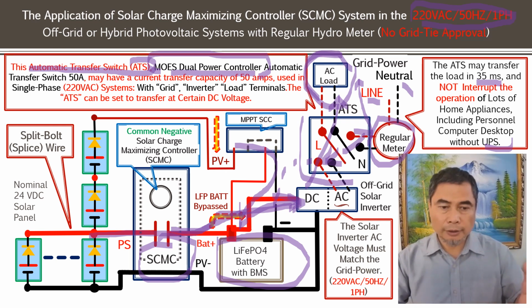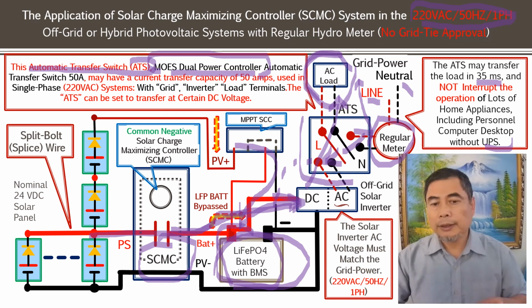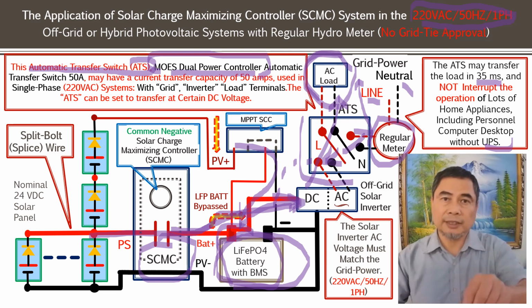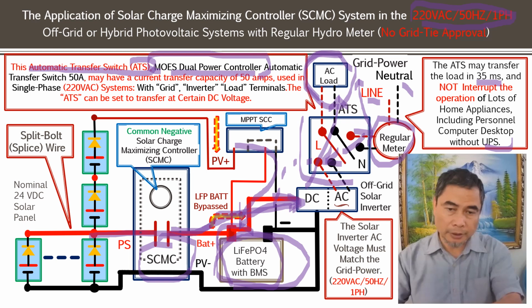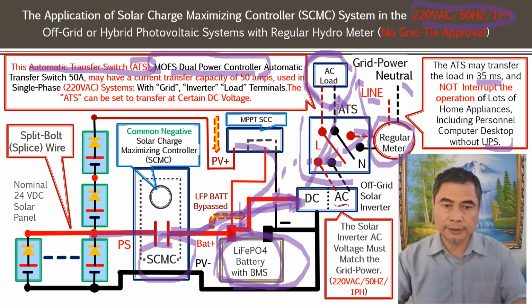whenever the solar conditions allow, whenever DC current is available from the system, we will be able to charge a LiFePO4 battery. You call it LiFePO4 battery too. It's a lithium iron phosphate battery, or LFP battery, as you call it. When the voltage builds up, this automatic transfer switch will sense the voltage and cut in again, disconnect power from the grid, and then use the power from the AC system.